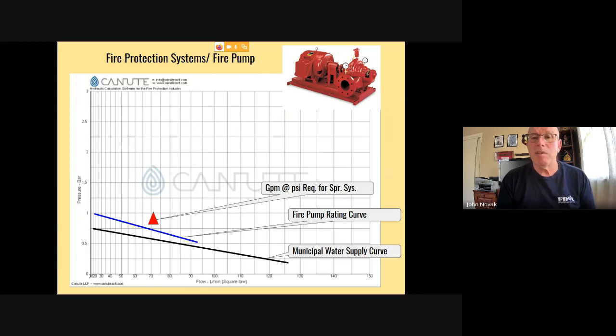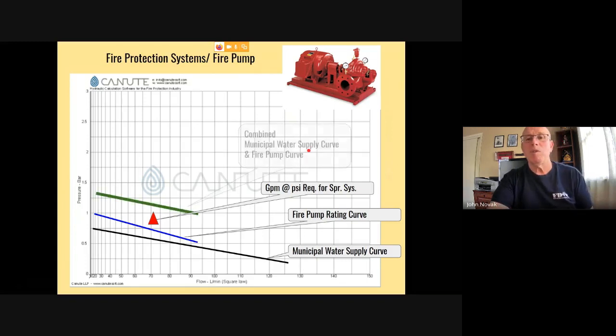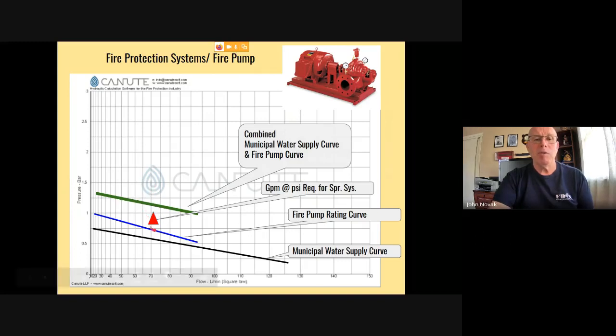So the blue line here represents the fire pump curve. Now, when we combine the fire pump curve with the municipal water supply, we come up with the combined curve, and now the requirement for the sprinkler system is below that water curve. So the water and pressure is adequate for the sprinkler system. Now, talking fire pumps are very expensive, so they're not going to source a fire pump that is going to be basically any higher in pressure or flow than is required. Big issue of dollars and cents with fire pumps.